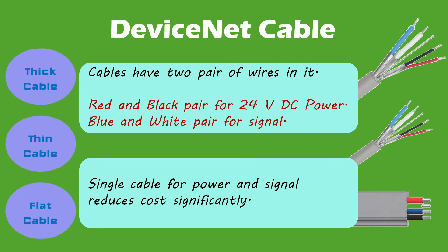In our last video, we came to know that DeviceNet uses three types of cable. These three types of cable have two pairs of wires. The red and black pair is used for providing 24V DC power to the connected nodes. The blue and white pair is used for signaling, i.e., information exchange. Power and signal are on the same cable, which is a great advantage in terms of cable laying cost, as only one cable is sufficient instead of separate power and signal cables.